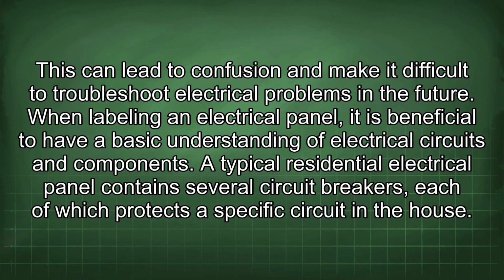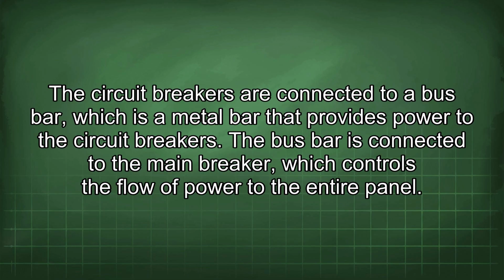When labeling an electrical panel, it is beneficial to have a basic understanding of electrical circuits and components. A typical residential electrical panel contains several circuit breakers, each of which protects a specific circuit in the house. The circuit breakers are connected to a bus bar, which is a metal bar that provides power to the circuit breakers. The bus bar is connected to the main breaker, which controls the flow of power to the entire panel.